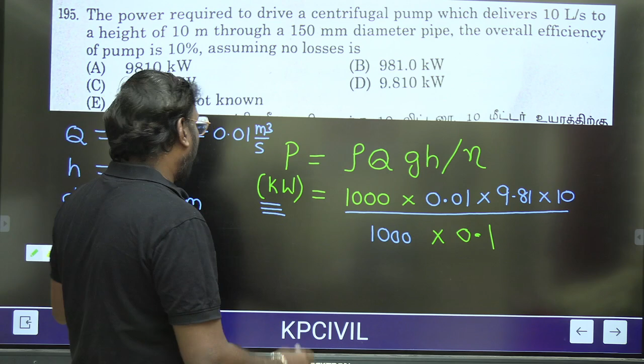Power is equal to rho Q g H, and you need it in kilowatts. Density of water is 1000. 10 liter per second we can write as 0.01 meter cube per second. g is 9.81, H is 10, divided by 1000 as you need kilowatts, the watts to kilowatts conversion. And most important, divided by efficiency, 10% in fraction, 0.1.